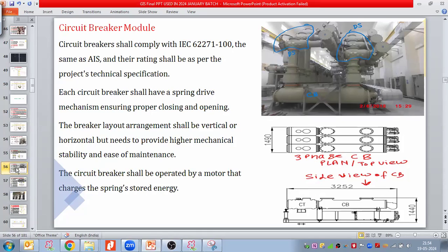This breaker equipment module shall comply with IEC 62271-100, same as in the AIS. So the breaker is not going to change whether you are working in AIS or GIS. The standard will be the same IEC, and the rating shall be as per the project technical specifications. Each breaker shall have a spring drive mechanism box ensuring proper closing and opening of the breaker contact.